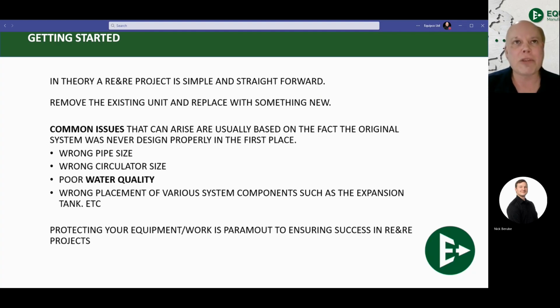You can sometimes get around this by using balancing valves, but it's also just as easy to actually size your circulator properly and correctly and let the system do what it's designed to do, which is heat adequately based on the heat loss. Next one on our list, poor water quality.